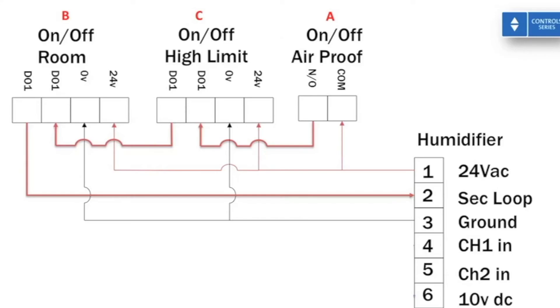The final step is to take care of the modulating loop — the second control loop on the humidifier — by using a jumper to fake a demand signal of 100%. Jumping typically pins 6 to 4 and changing the respective parameters in the humidifier's keypad for the corresponding voltage range tells the humidifier to run at 100% as long as the first security loop is completed. Recall that all three devices must complete the loop for the humidifier to run. Your wiring is now complete.